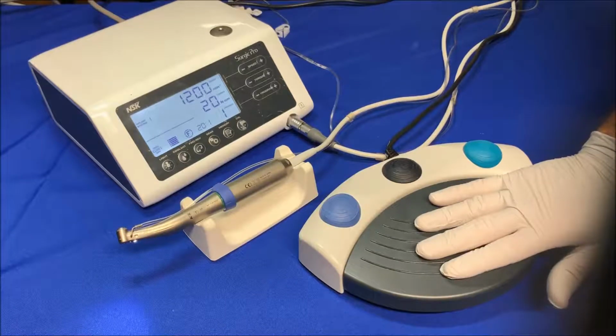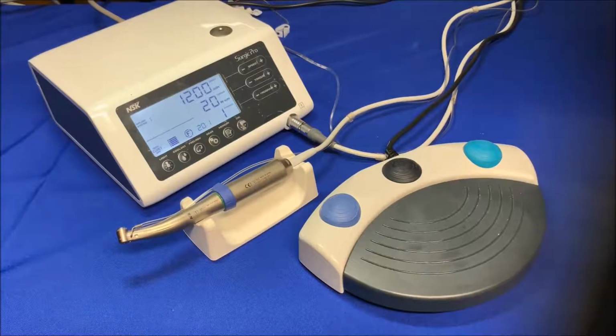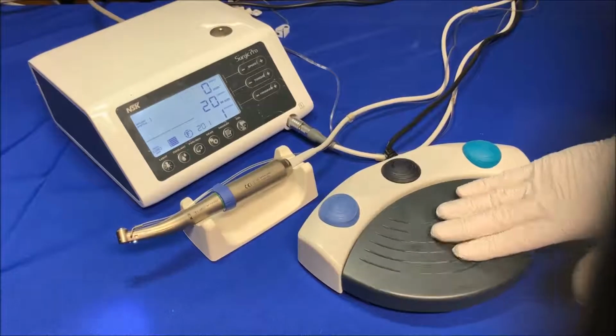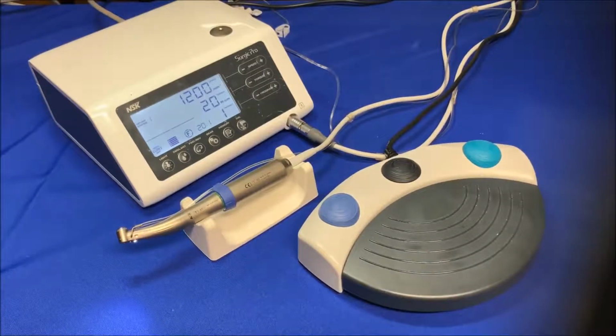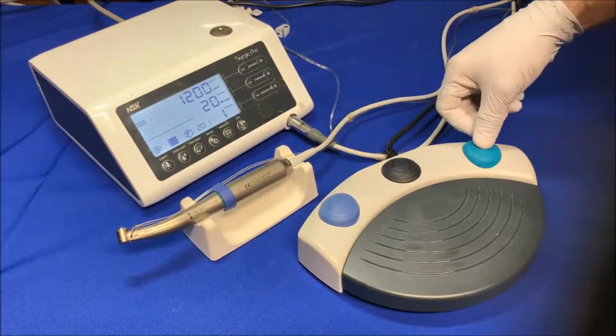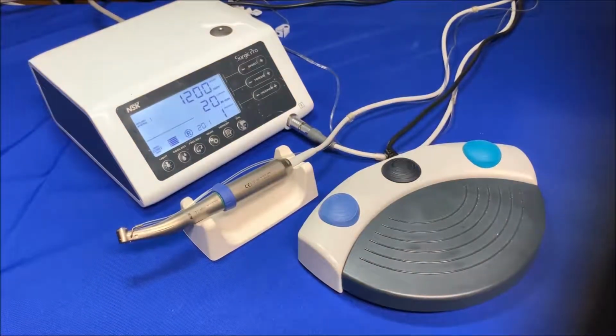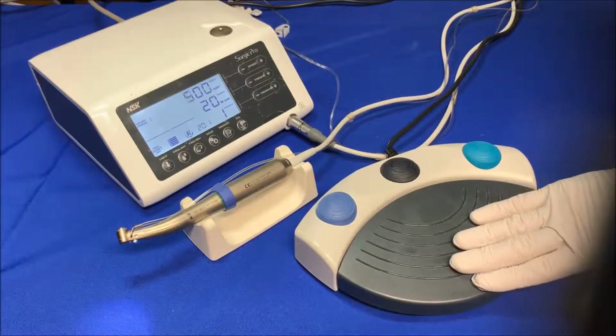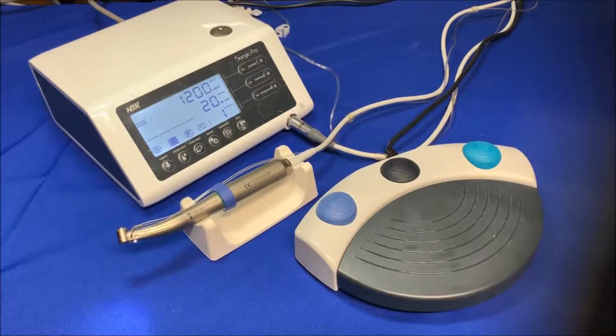If the drill is stuck in the bone by reaching the maximum set value of the torque, you'll get an error message with a beep sound. Tap on the speed pedal to clear the error. Press the green button on the foot control to change the rotational direction, then step on the speed control pedal again to release the burr. Now change the rotational direction back to forward again. You're ready for another round of drilling.